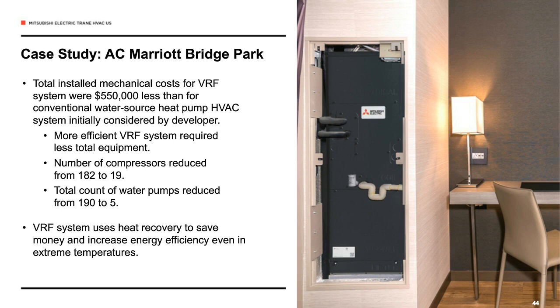Now, I know Mike talked about this, but the advantages of water source VRF systems in extremely cold climates include the fact that with water as the heat sink for all the VRF system's equipment, they can be installed indoors. Indoor installation means the equipment is better protected from outdoor conditions and can deliver optimal performance and even lower degradations of performance in extreme cold. So with harsh winters and temperatures that dip below freezing, water source VRF helps improve the guest experience for the AC Marriott.